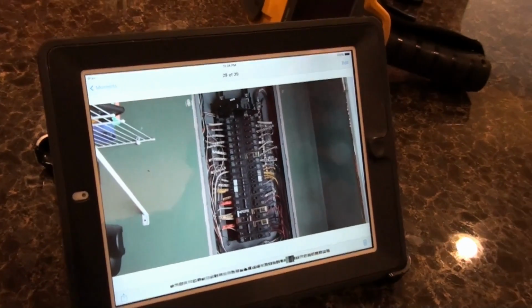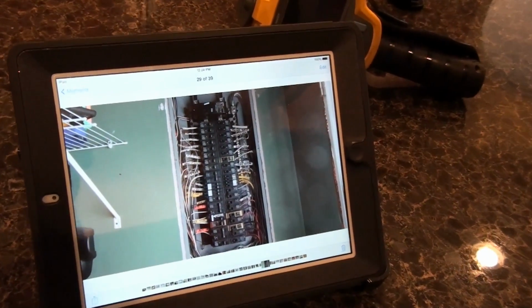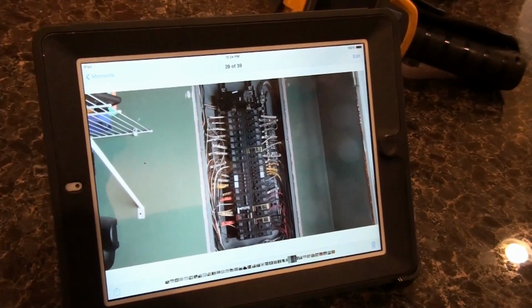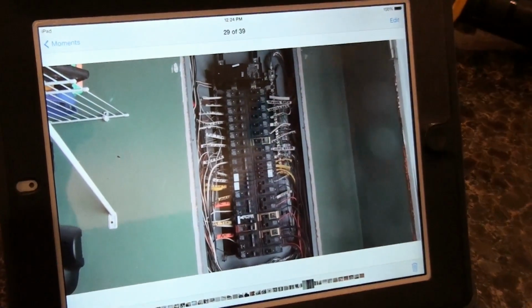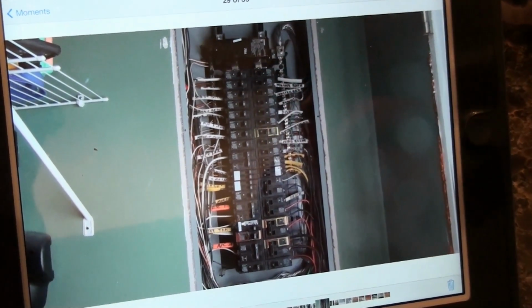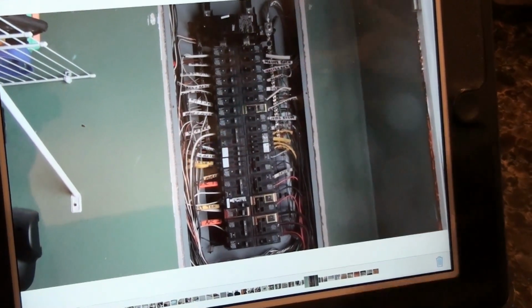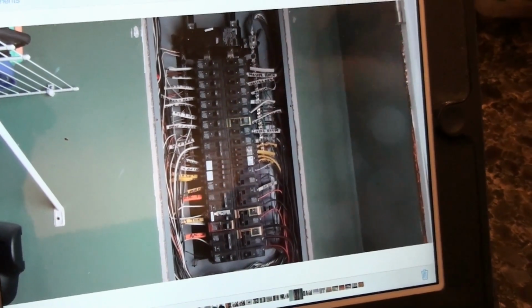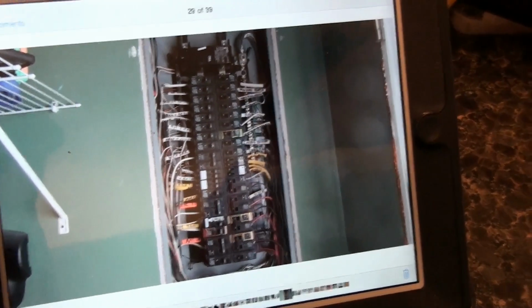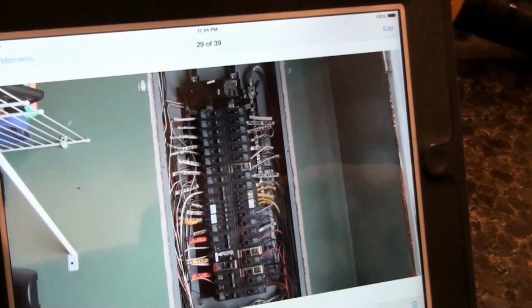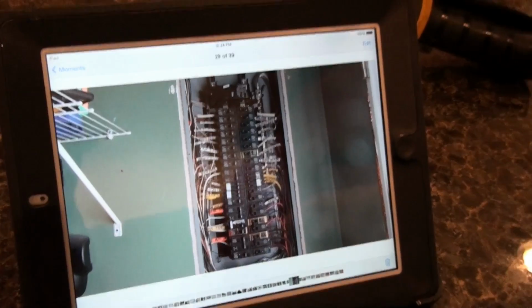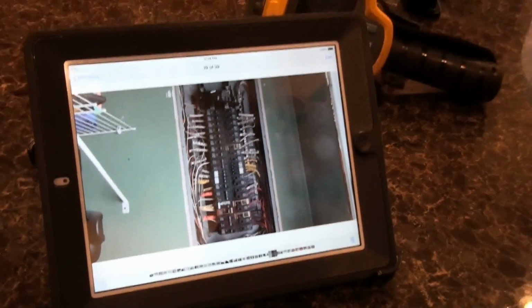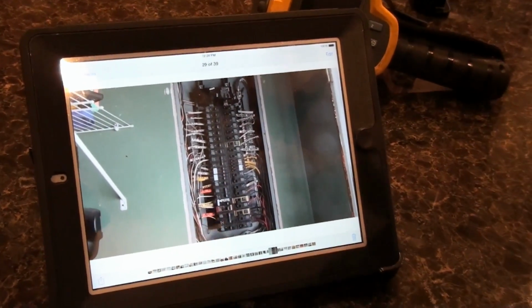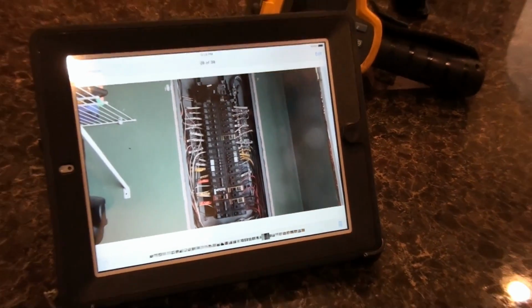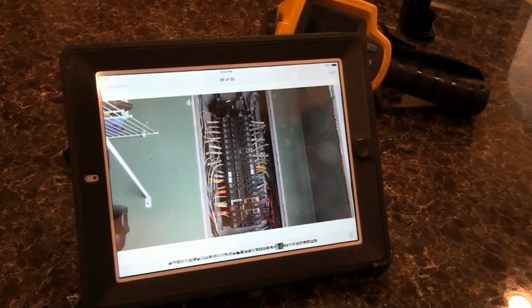Electrical panel: everything is fine. It is full, so if you were going to add any additional appliances or a hot tub, you're most likely going to have to upgrade. This is a 200 amp, 208 panel, so you'd probably have to add an additional 60 to 100 amp service panel to do any additional upgrading.